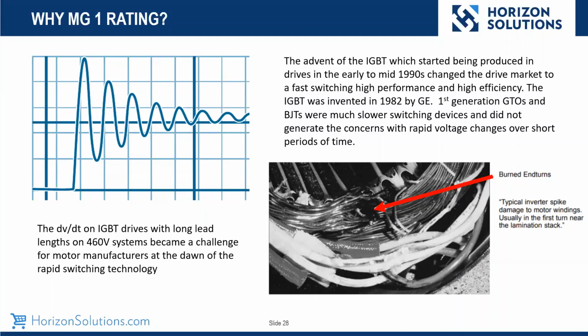The only choice you have here is to send it out to an EASA shop and get them to rebuild this or buy a new motor. A lot of manufacturers nowadays, 50 horsepower and under, they're just replacing the motor with a new motor. Next slide.